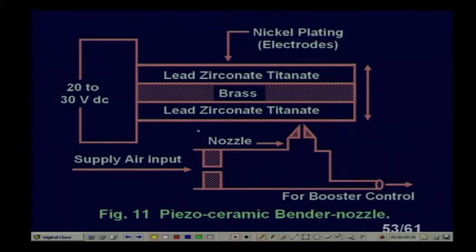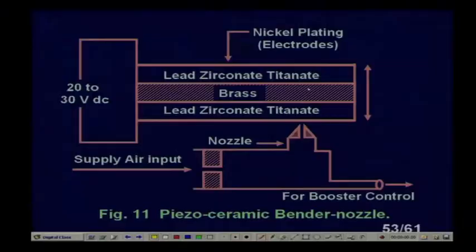So many other components we have eliminated here, because there is no coil as such. We apply the voltage directly, and since this is a bimetal sort of arrangement, ceramic and brass, it will bend in one direction or the other. When the voltage is applied, due to the piezoelectric effect, this will make the flapper move close to the nozzle or away from the nozzle.